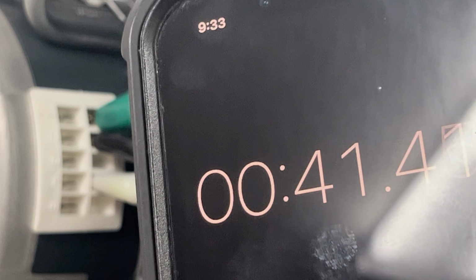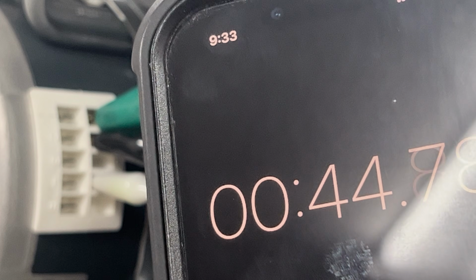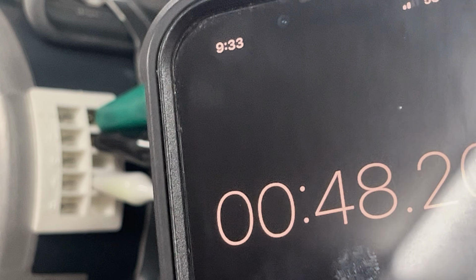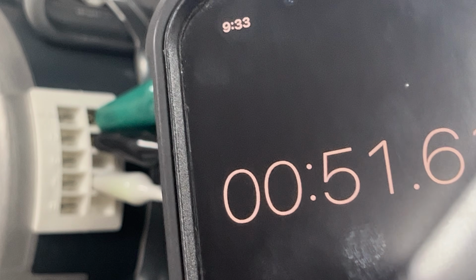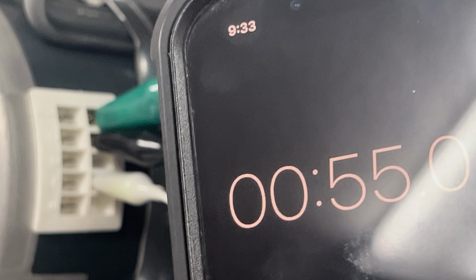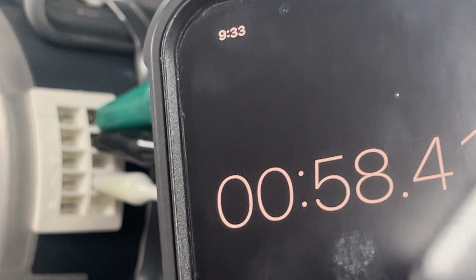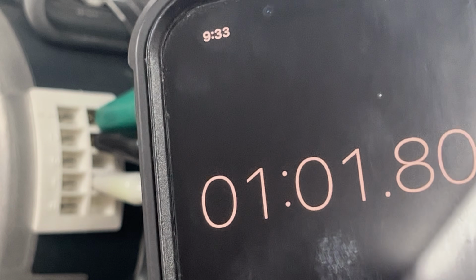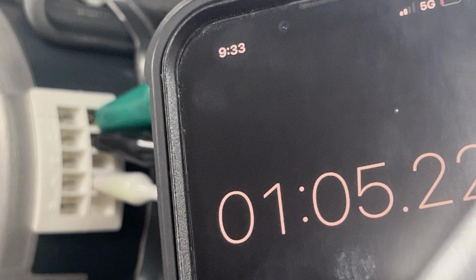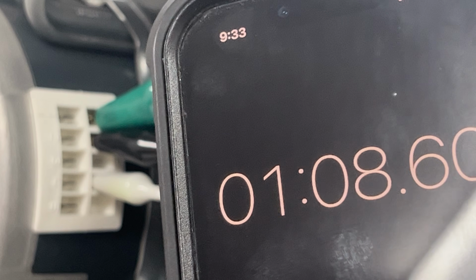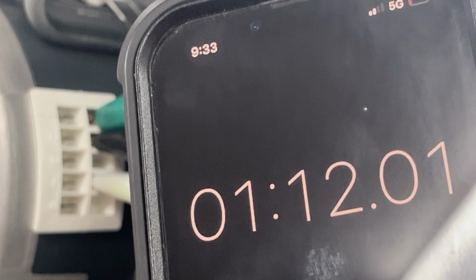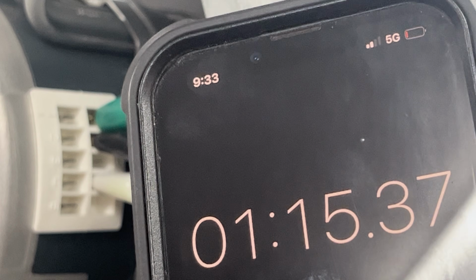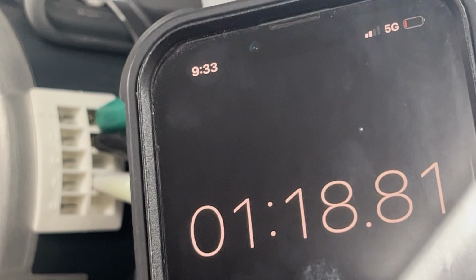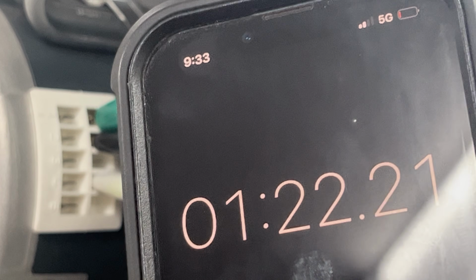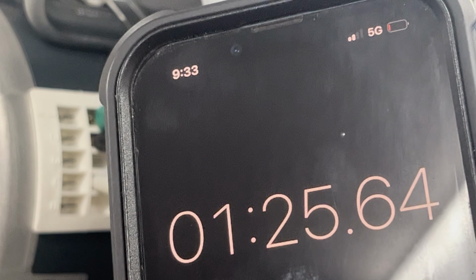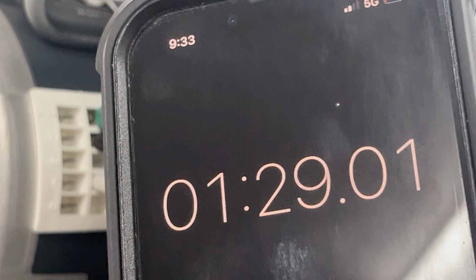Like I said earlier, if I were to reapply voltage to any one of those terminals 1 through 5, this delay is going to start all over again the moment I release power. So you need to be patient, and if you think your module has a bad relay where the module's keeping the motor energized because the contacts inside of it are stuck in a closed position, just like a relay could stick in a closed position, and a lot of times these things don't shut off, that's what's going on. Same thing, a lot of times you apply low voltage to them and they won't come on. Try different speeds. If you think your motor won't come on, you have 1, 2, 3, 4, and 5. Try every one of those, put 24 volts on each one of those before you condemn the motor, because it may just be a bad module.